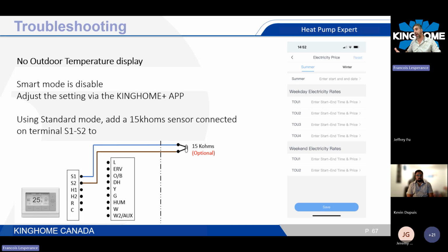So you need to go back to the app and make sure everything is up and running to use the smart mode. Or, if you are in standard mode, you need an extra 15 kiloohm sensor connected to the outdoor unit on S1, S2 at the thermostat. We do have those 15 kiloohm sensors. I don't have the part number with me, but that's the kind of information we can share with you after the presentation. If the homeowner wants the outdoor temperature without using Wi-Fi, it will be on S1, S2.